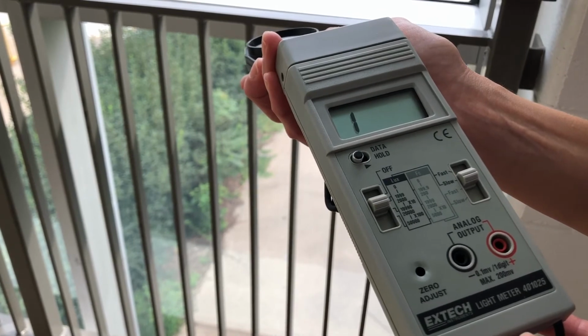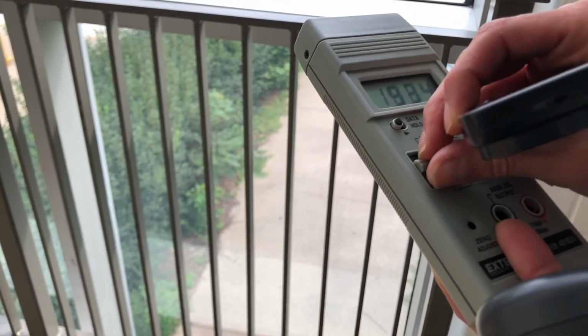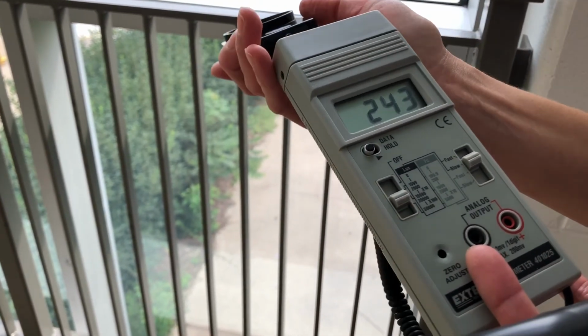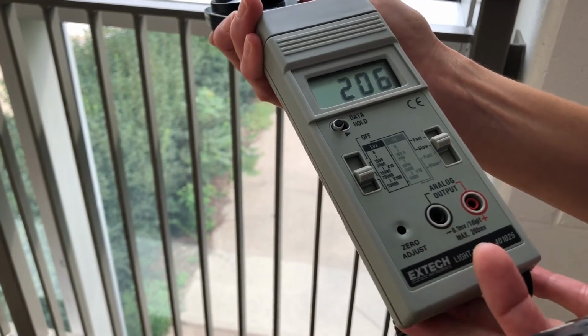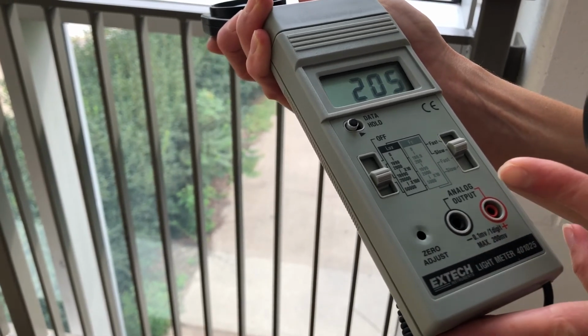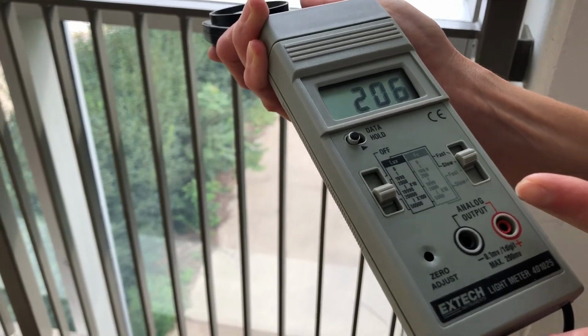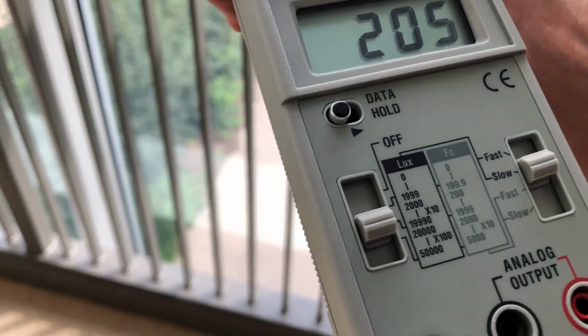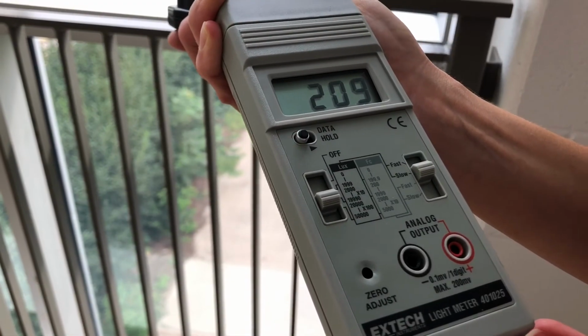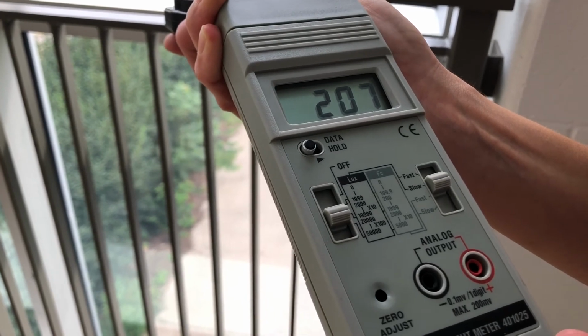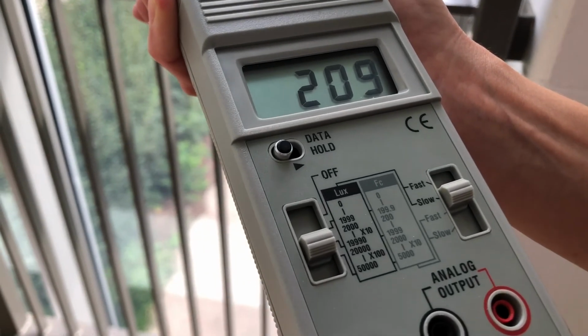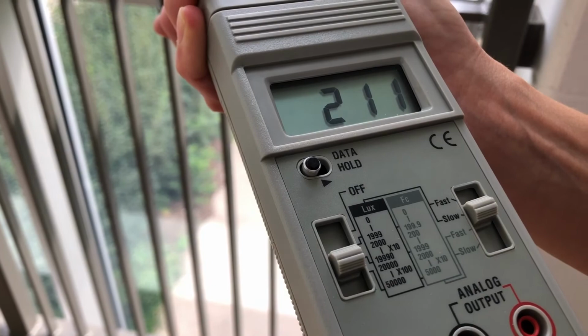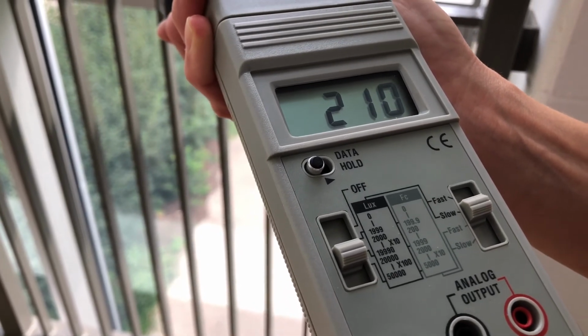If it's showing a 1, you need to toggle to the next category, and then you might need to multiply it by the value that's located there. So by multiply it by the next category, it's showing that you would have to multiply it by 10, so therefore it'd be approximately 2,000 at this point, just over 2,000 lux.